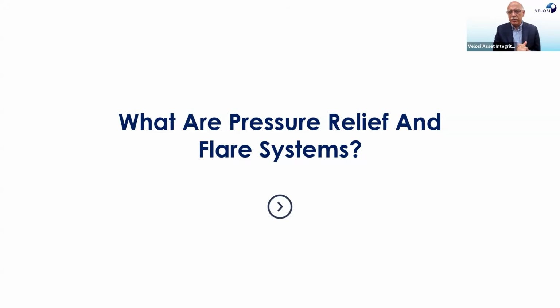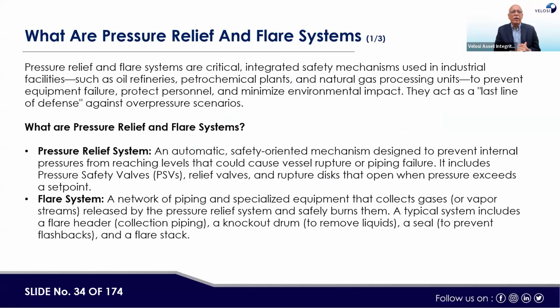So that system, where in case of system redundancy, if you have to shut down the plant, is where those chemicals or gases or hydrocarbons should go. That goes to the relief system. A PSV is open to the relief system. The relief system goes to the flare knockout drum, and there is a flare, and you can burn all those chemicals. So that system is normally called the pressure relief and flare system.